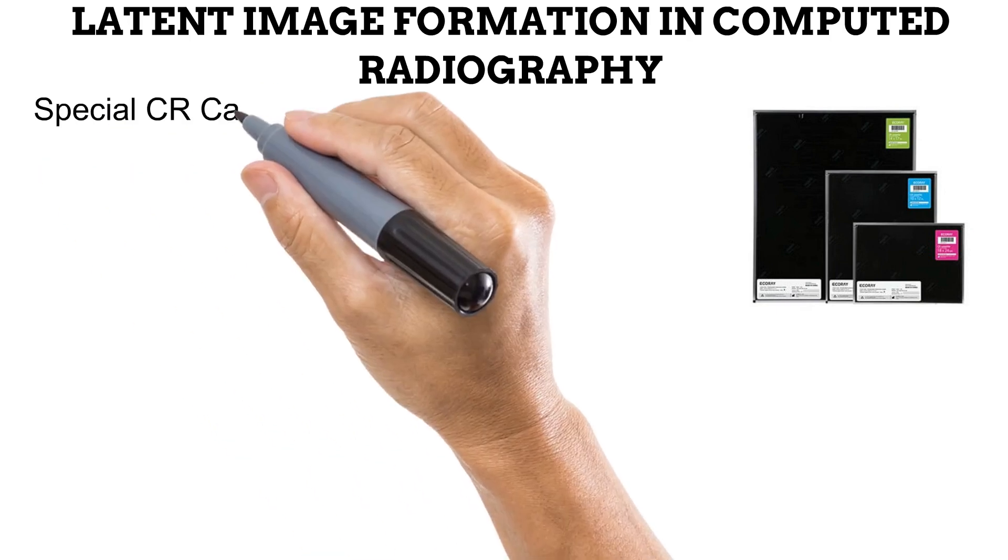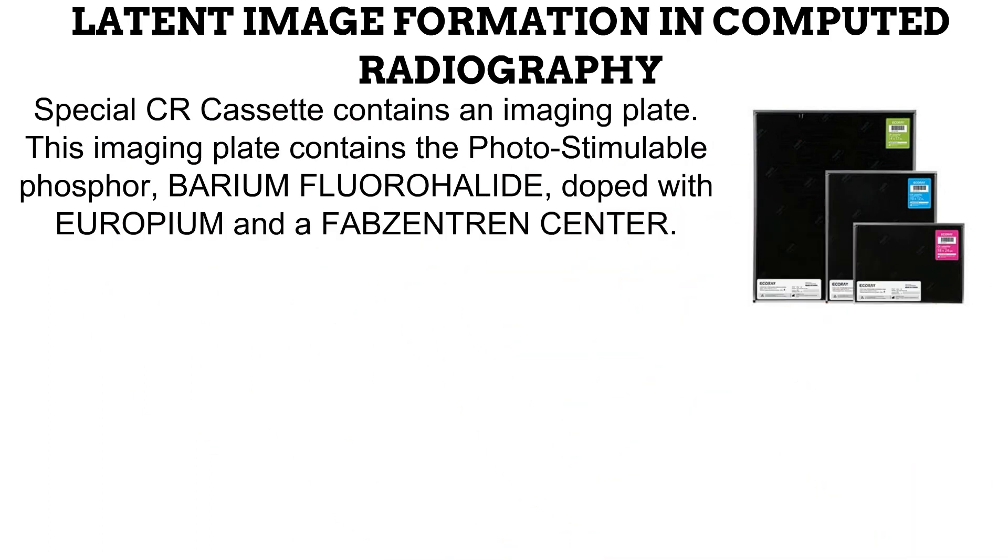That takes us to the process of latent or invisible image formation in computed radiography. What you have on your screen are different sizes of the type of cassettes or image receptors used in computed radiography. You would observe that they are very similar in appearance to the cassettes used in film screen radiography, and these cassettes will also fit into the same bucky trays as film screen radiography cassettes. However, unlike the film screen cassettes, these computed radiography cassettes do not house removable films. The radiographer has no reason to open these cassettes between examinations, like is done in film screen to place a new film for exposure. These computed radiography cassettes contain a structure called an imaging plate, which looks a lot like an intensifying screen and contains the photostimulable phosphor material, barium fluorohalide.